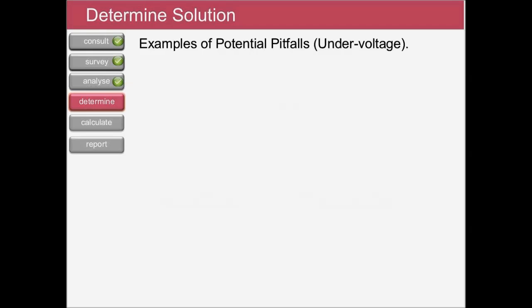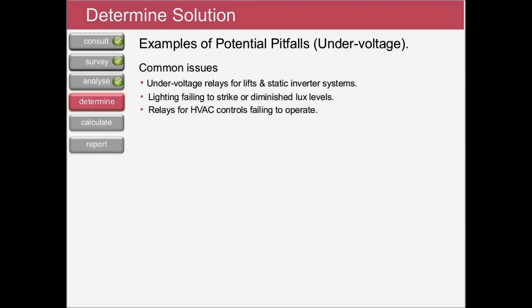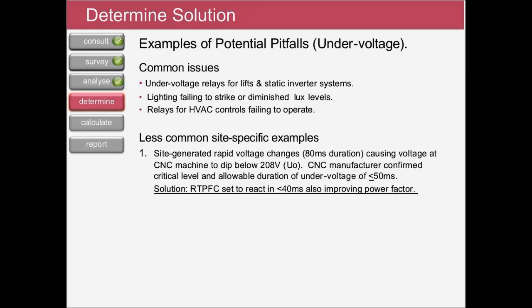So here we've got some examples of equipment failures that can often be attributed to voltage mismanagement. Unfortunately, some of the more common issues have cast a shadow of doubt and scepticism over the VO market. Historically, these issues have included undervoltage relays for critical systems dropping out, lights failing to strike, and lux levels being compromised in areas illuminated by voltage-dependent fittings, to name a few.